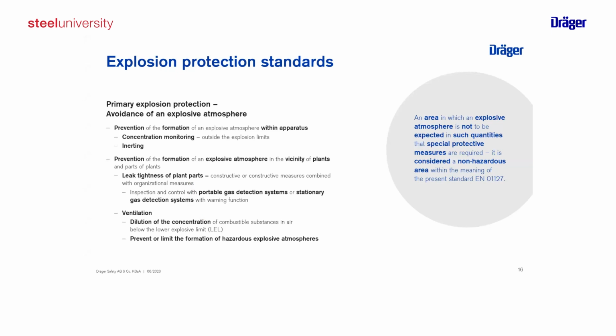If we have an installation inside a building, then we can use ventilation, for example, to dilute the concentration. So by constantly adding fresh air, we reduce the concentration of our flammable substance and keep it below the lower explosion limit. By this, we dilute and we prevent or limit the explosive atmosphere. Important to know is this is only necessary when we expect quantities of a gas or vapor such that special protective measures are required.